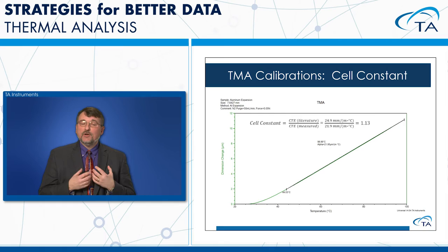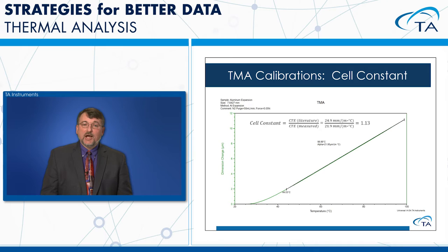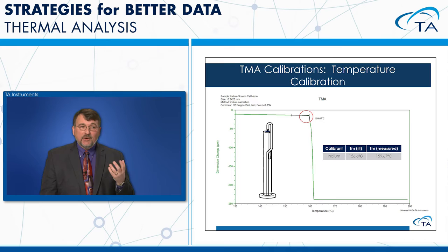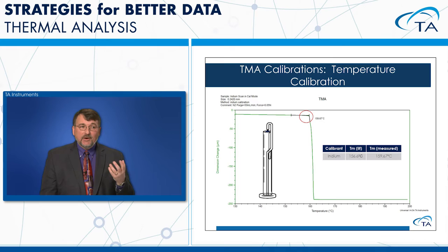This cell constant gives us the best measurement of coefficient of thermal expansion when running samples. For TMA temperature calibration, a melting standard such as indium is placed on the stage with a probe on top, and we heat up and look for the indentation when the sample softens. The probe penetrates at 159.67°C; that value is entered into the table to correct for the temperature offset.